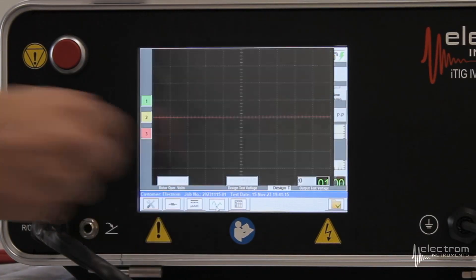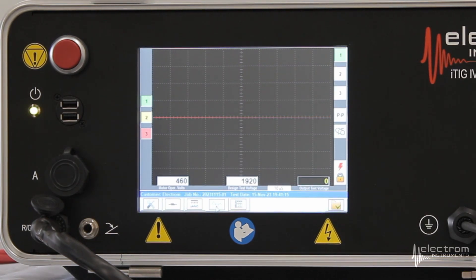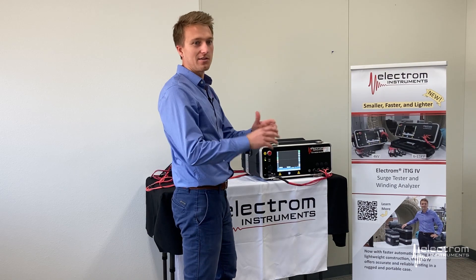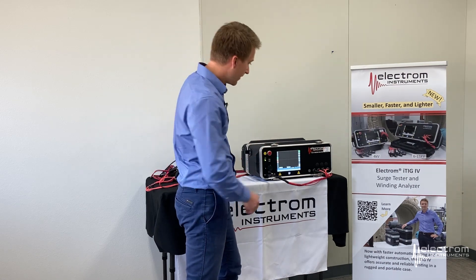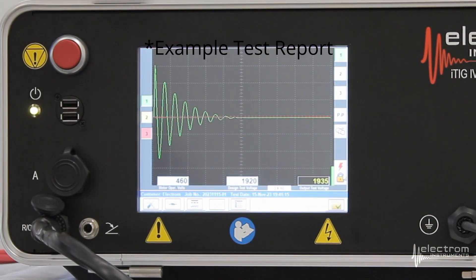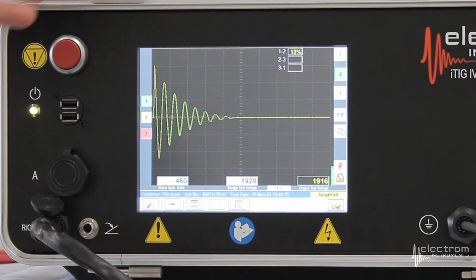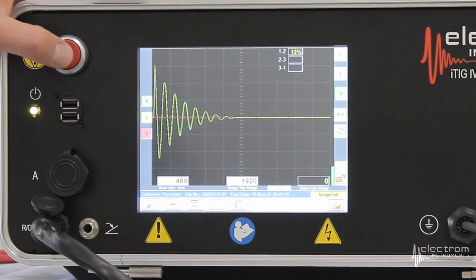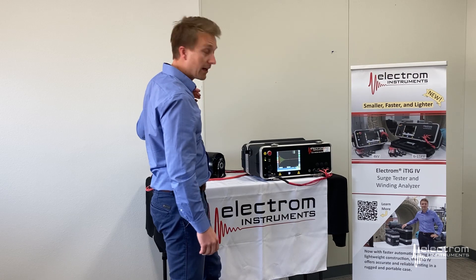Next up is our surge test — this is the oscilloscope screen. With modern test equipment you don't need to set the time base or voltage scale; you tell it what voltage to go to, which lead to energize, and click the button. Lead 1 is selected — arm the instrument, press the red button. It will automatically make all oscilloscope adjustments and drive the voltage to 1920 volts. Then Lead 2, arm, red button. Lead 3, arm, red button. We now have the line-to-line surge comparison for phases 1, 2, and 3. As you can see, they don't quite overlap — that's expected since we are testing a concentric ground application.